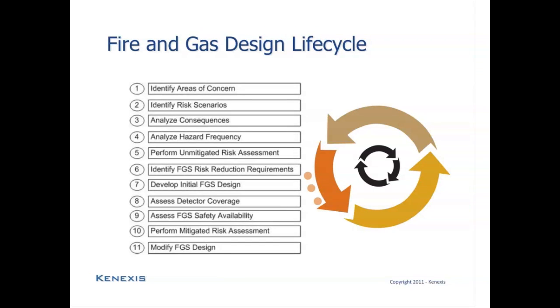After that, we'll be able to perform a mitigated risk assessment. So now we originally looked at the risk without the benefit of a fire and gas detection and suppression system. Subsequently, we will look at the risk after the mitigation has been put in place. If the mitigated risk is acceptable, then we leave the initial fire and gas system design as being validated and move on to the next zone or the next system. If it does not achieve the requirements, then we'll analyze the areas where the design failed, propose a new design, and then go back to step 8 where we assess the coverage and continue in a loopwise fashion until the proposed fire and gas system meets the requirements of the tolerable risk.